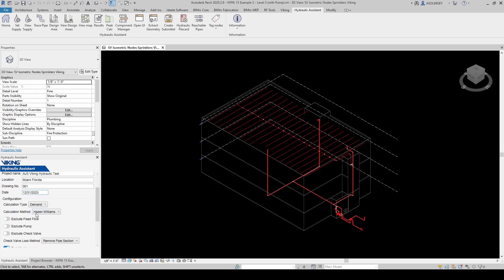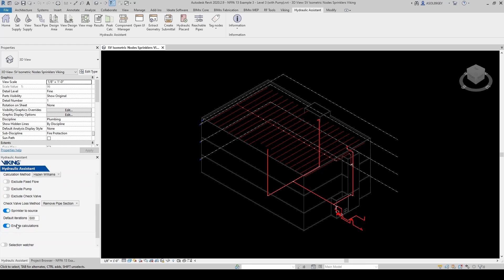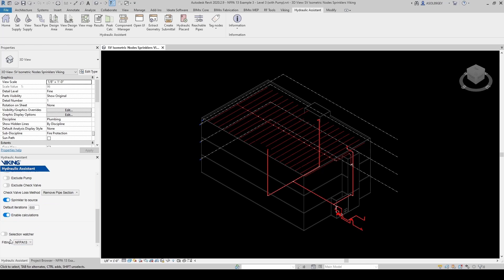I'm going to keep the calculation type as demand. And for calculation methods, you have two options. You can do Darcy-Weisbach or Hazen-Williams. I'm going to keep all these defaults. I want the calculations from sprinkler to source. So it's going to come all the way from the most remote area back to our source. Default iterations is 500. That's fine. Enable calculations.